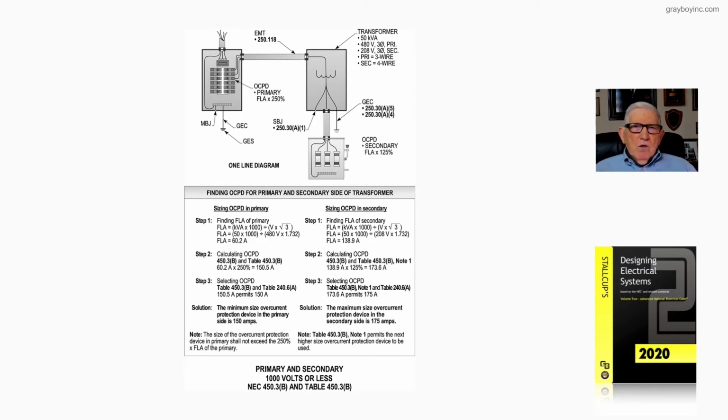If we had an overcurrent device that would clear at 0.0084 seconds, then it might be a little higher than 25 times. So this was an estimate, though. We're not saying that that would give you the exact inrush value. Now, what we would do on most all of our transformers, we just figure 10 to 12 times, and that was a pretty good estimate to use.